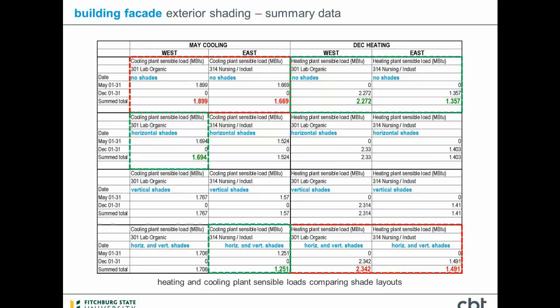And so as we see for cooling, having no shades was the worst scenario, both in the east and the west facing. If we're looking at the heating side, then having vertical and horizontal was the worst because we were blocking out the beneficial sun. And so by mapping on a series of iterations, it gives you the ability to start fine-tuning different orientations of the building and optimizing the shading devices that are going to have the best and most effective impact on the building.